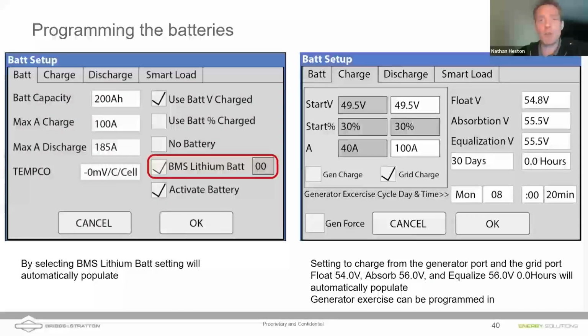On the right side of the screen, we've switched from battery to charge and discharge now. If we had selected voltage, then we would be able to program those values in for a voltage. You have generator settings there as well as grid settings. And so we're giving our maximum values for charging from the grid there. If you had checked the generator box, you'd be able to provide those values for the generator when the grid is unavailable. For our batteries, the float voltage is 54. The absorption voltage is 56. That's the voltage you get to when you're doing that constant current charge cycle at the beginning. And then our equalization, we're going to set that to 0.